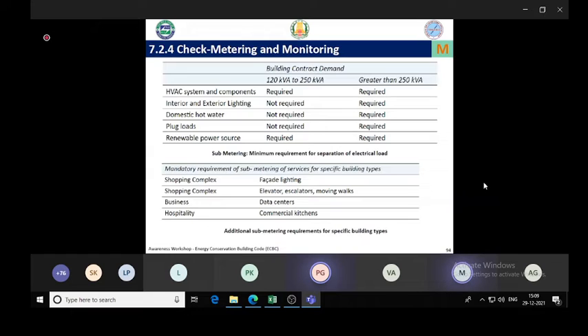Okay. Now we also need to have separate meters for the major loads like HVAC, interior lighting, hot water, etc. In case our load is more than 250 kVA, then we need to monitor all the major components, lighting, HVAC separately, submetering should be done. So again, for specific buildings, if there is a data center within the building, that has to be submetered separately. And for a shopping complex, we need to again submeter our elevators, escalators, and so on.